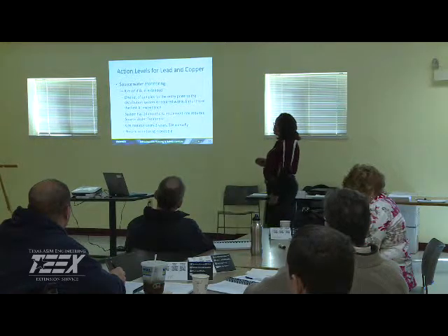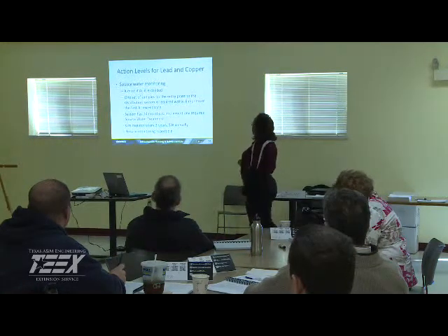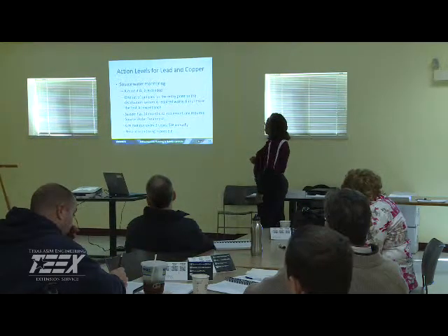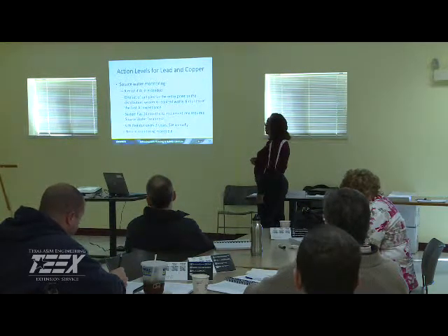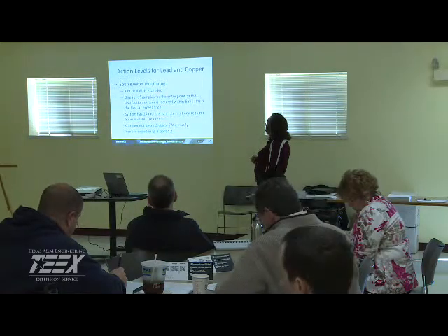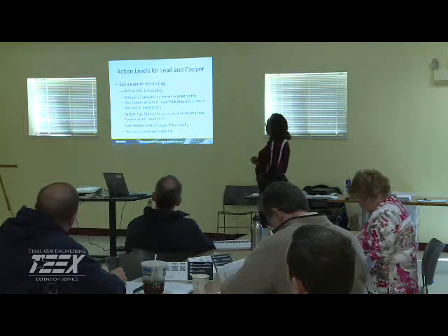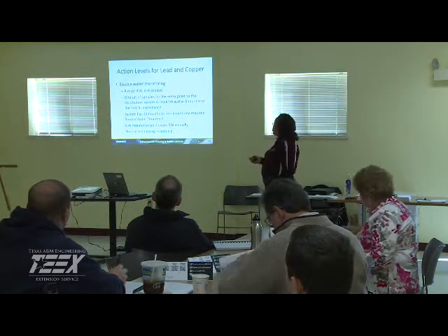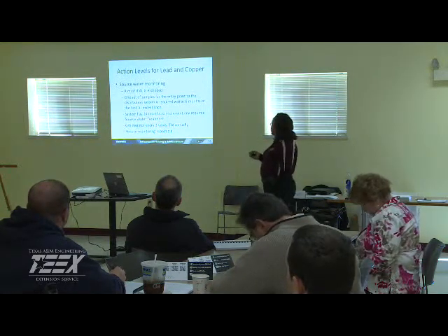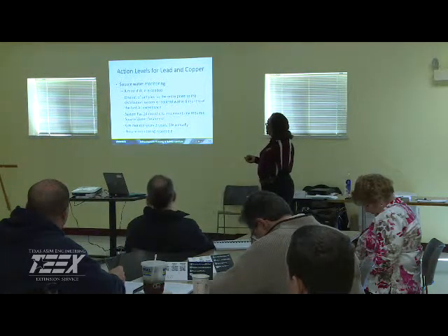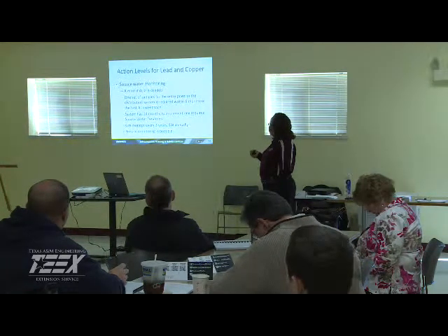You also need to do source water monitoring. Again, you want to make sure that you're meeting or you're below that action level. Source water monitoring when you exceed it is a must. One set of samples for every entry point to the distribution system is required within 6 months of your first exceedance. Systems have 24 months to implement any required source water treatment.